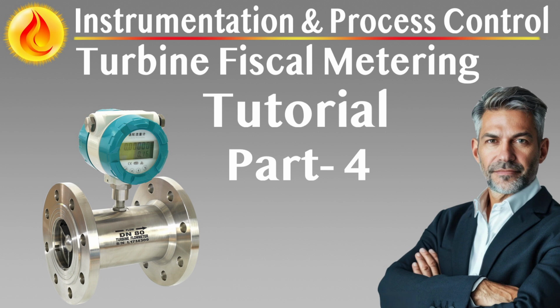Dynamic functional testing. Dynamic tests must validate real-time interaction between system components. This includes automated proving sequences, flow control valve response and modulation, alarm generation under simulated failure conditions, meter selection and deselection logic, valve positioning and seal integrity checks, water cut system switching, signal transmission between skids and control system.